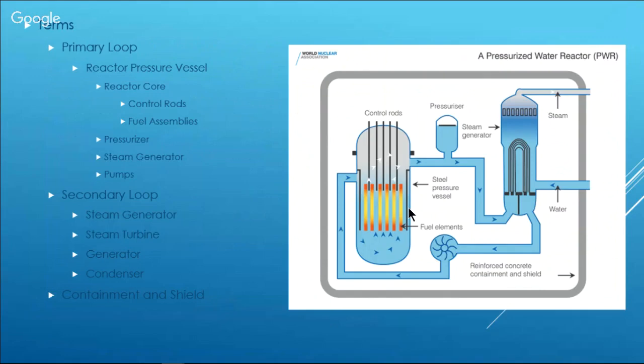They will share their heat with now empty air, and air is not a good heat removal mechanism. No, very poor. So what's going to happen is the fuel pellet will heat up and expand into the metal cladding around it. That's zirconium. Yeah, the zirconium, the cladding. And that could either pop the cladding, you'll get a pellet-clad interaction, where the pellet expands to pop open the cladding, or it gets so hot that it just melts the cladding.